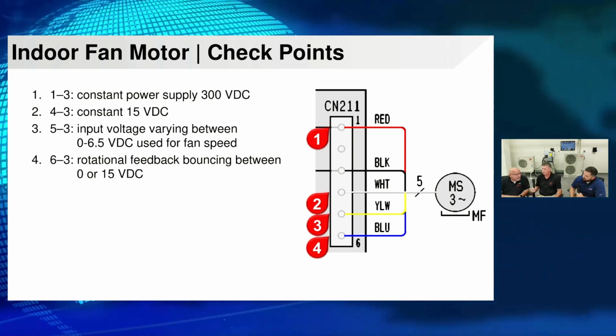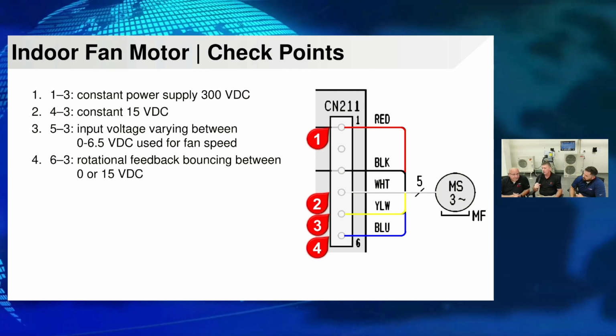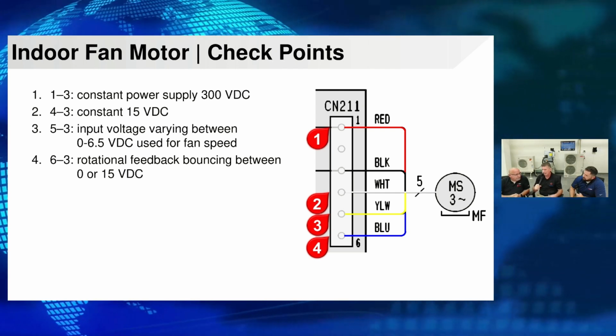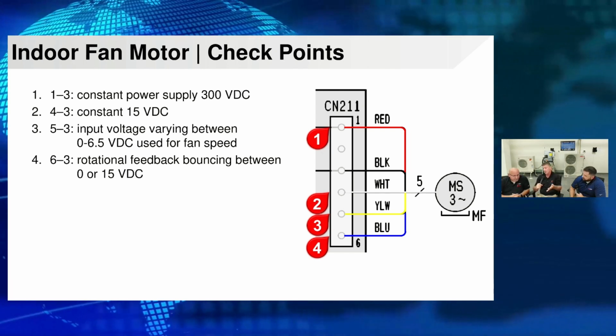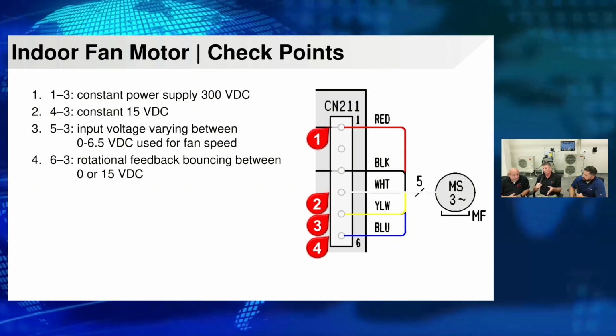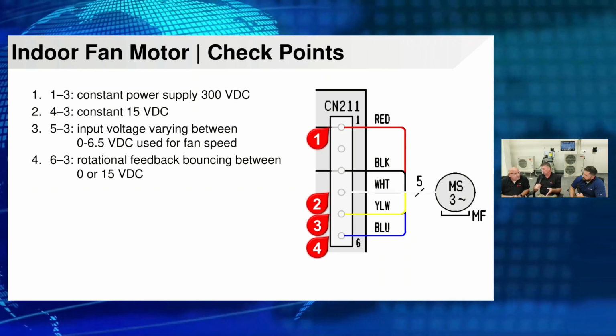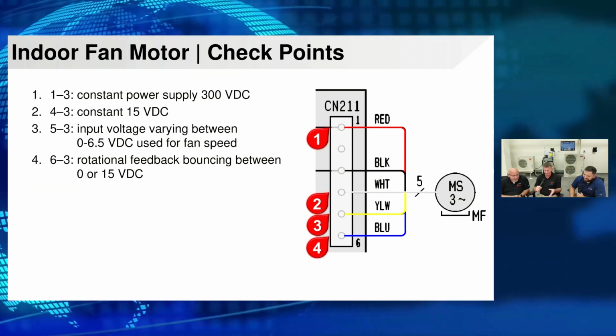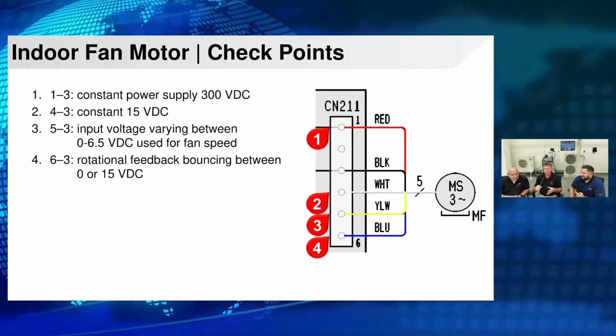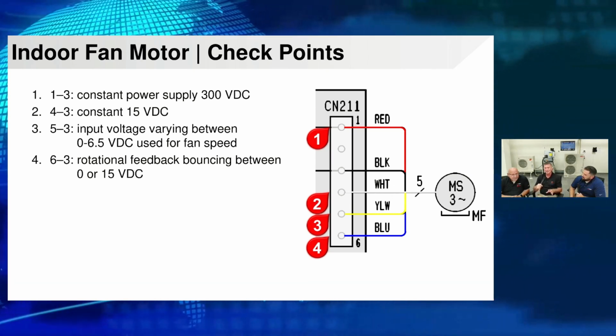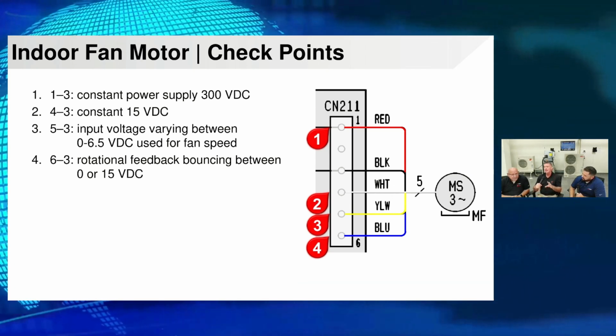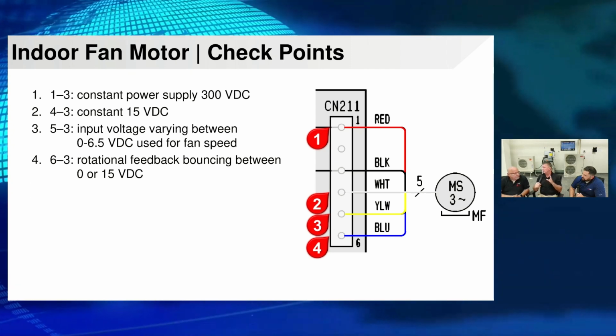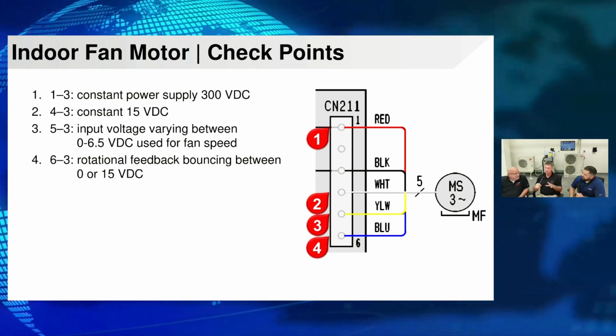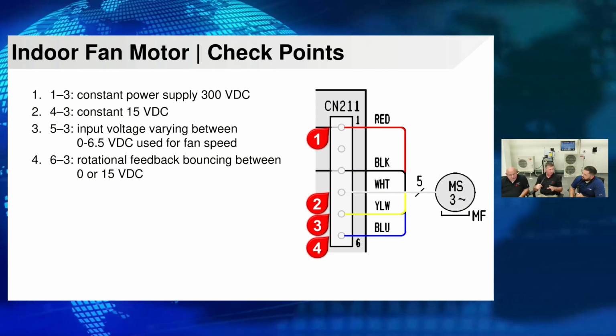Yeah, absolutely. And I've heard that before, and I've always known it's because we've had positive energy there. But that just helps you understand that even our plug is designed to put a space between the wires so that they can't. Right, exactly. It was intentional. So we want to make sure that we're keeping those as isolated as possible, removing power. And when we're talking about DC voltage that is being supplied from a capacitor, it's very important to allow time for those capacitors to discharge.